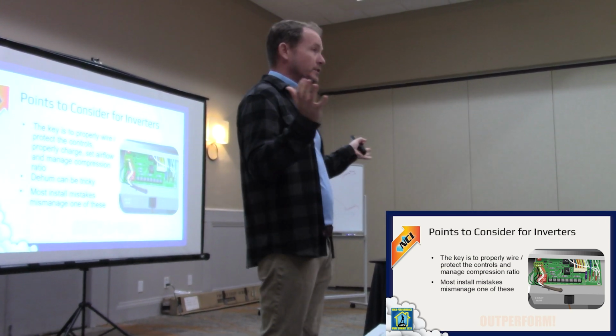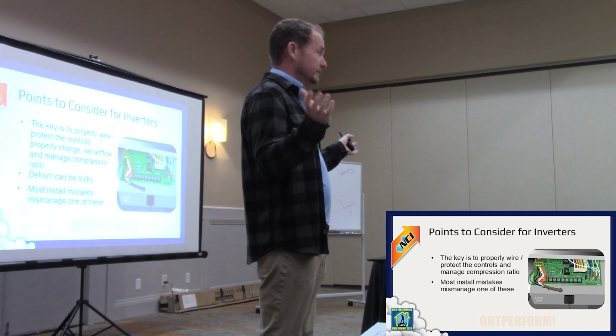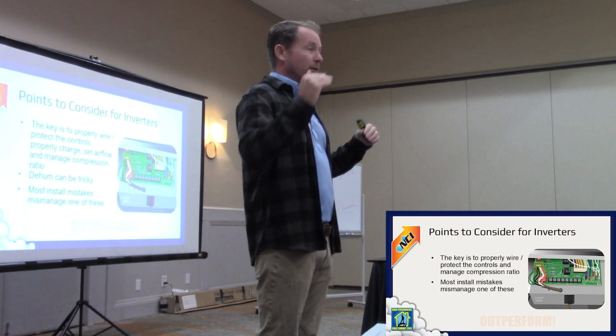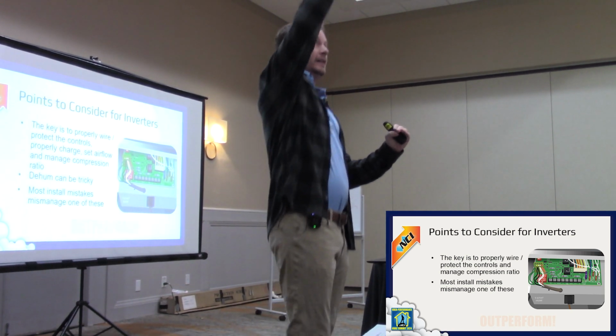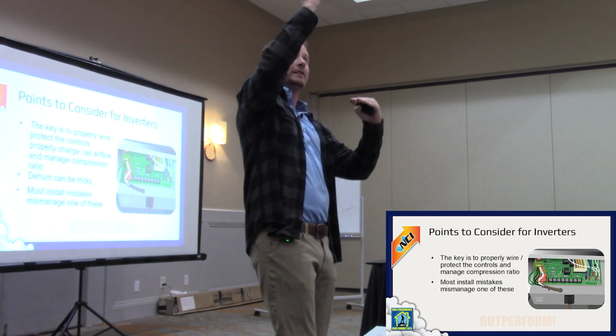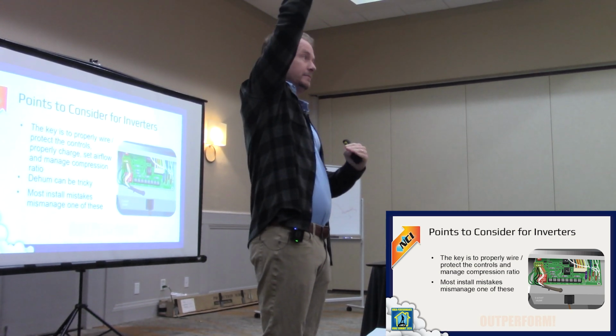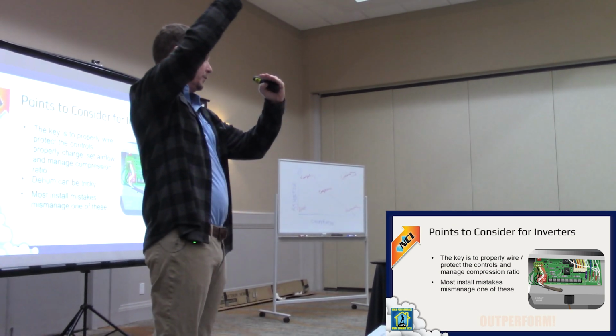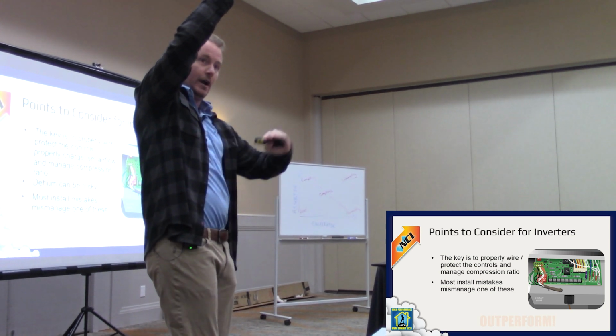On a heat pump, where's your condenser when you're in heat mode? Inside, right? So if we want more heat out, we want to increase condensing temperature, which separates compression ratio. If we want to wring more moisture out, we want to drop evaporator temperature, which also separates them.